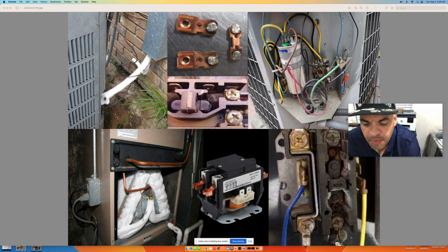Okay. A lot of people think that when a unit freezes up, it's going to be just low Freon or an actual frozen coil. Also, a dirty filter. Another reason why a unit can actually freeze up is a stuck contactor. Why? Because when your contactor is in the stuck position and your AC is off, your blower motor in your attic or in your garage, wherever you have your air handling unit or furnace, it's going to turn off. And if you don't have any air blowing across your coil, you don't have any of that warm air, the coil will get too cold and freeze up.